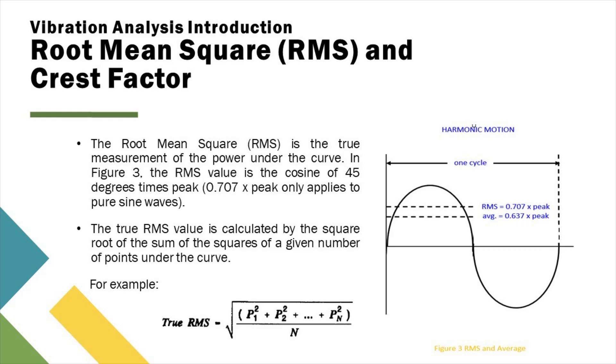The root mean square, RMS, is the true measurement of the power under the curve. In figure 3, the RMS value is the cosine of 45 degrees times peak. 0.707 multiplied by peak only applies to pure sine waves.